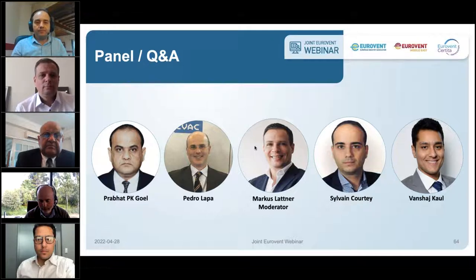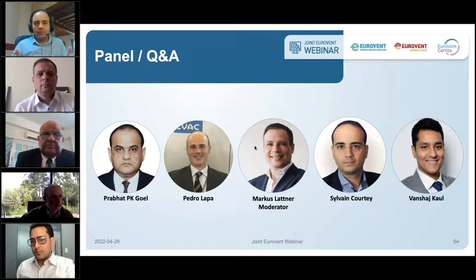So already in Europe, there was some debate about imposing heat recovery systems with minimum limits. I think the Eurovent approach is maybe more consistent because it's a holistic approach which takes into account all parameters: the air speeds, the heat recovery efficiency, the heat recovery pressure drop, the fan efficiency, and all these have to be considered. So if something has to be done, maybe I would suggest that it relies on a method which is more or less aligned with what Eurovent has been doing.